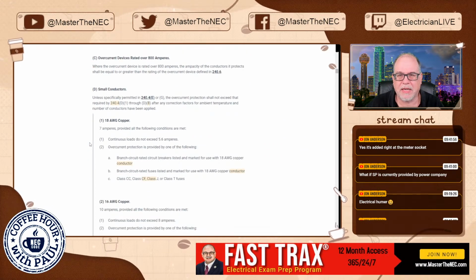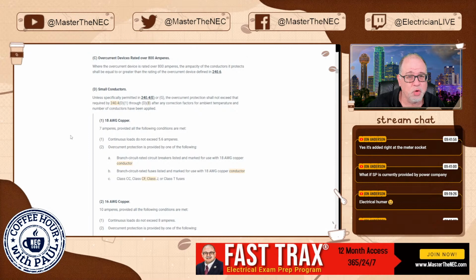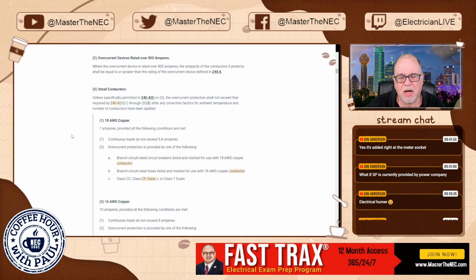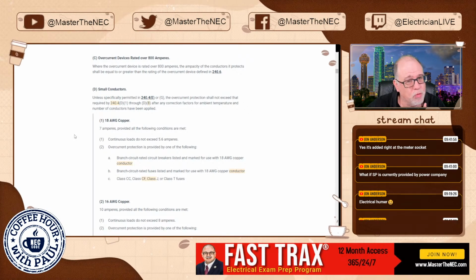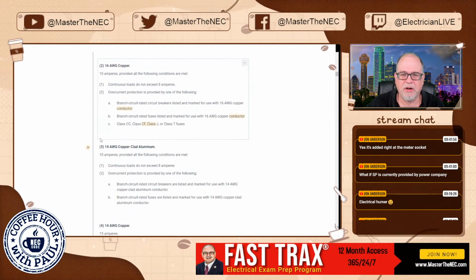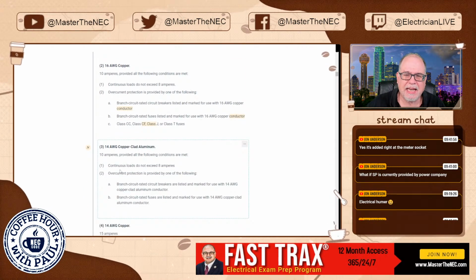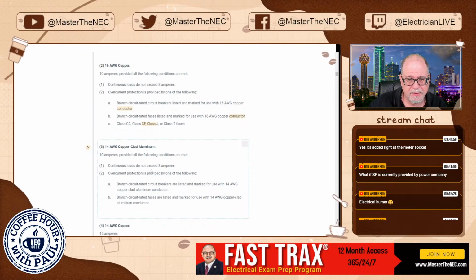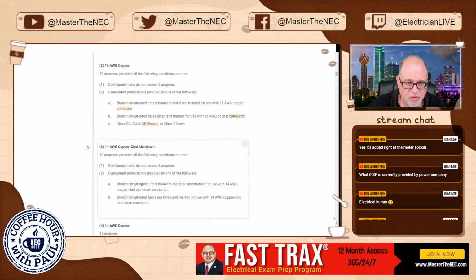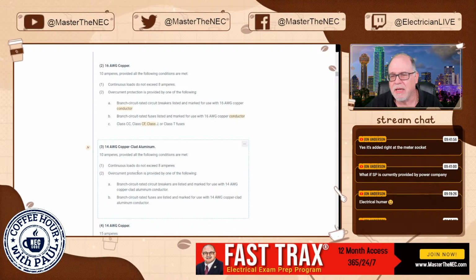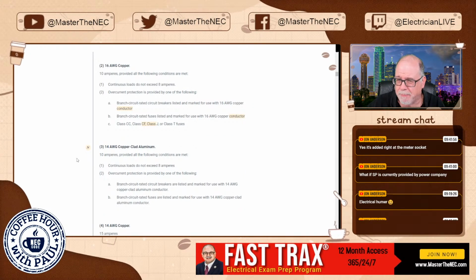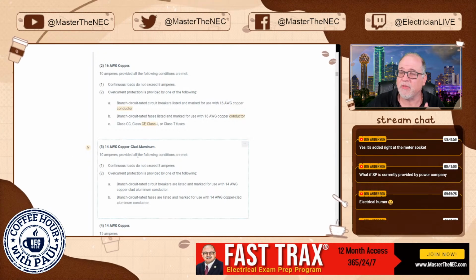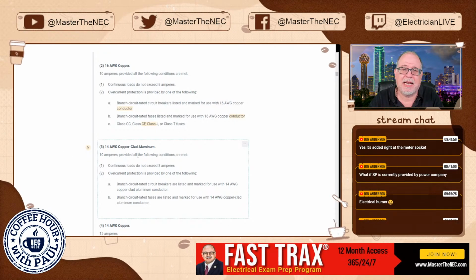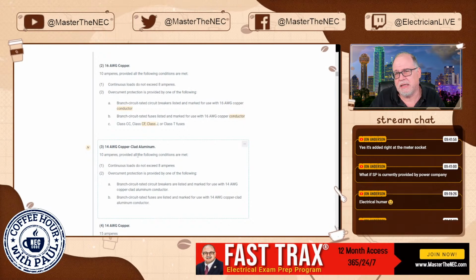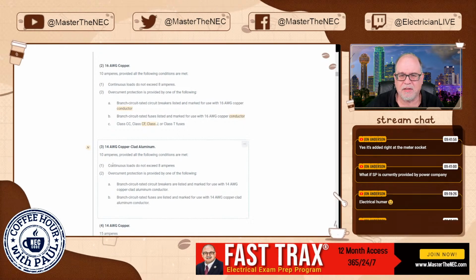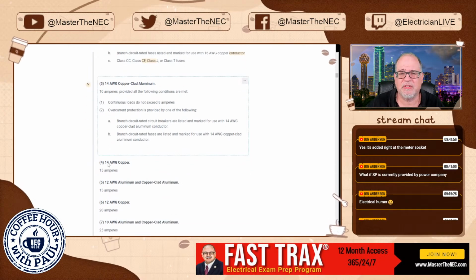The next thing that we want to look at is the inclusion of some new small conductor ampacity, overcurrent protection rules. I shouldn't say ampacity, overcurrent protection rules. So you'll see here that 14 gauge copper clad aluminum was added for 10 amps. Okay. And continuous loads, you can't exceed 8 amperes. And this is only really for lighting type of loads. But at least now we're giving you some ampacity ratings for these conductors. And it's very common to use 14 gauge copper clad aluminum for some control applications, right? So here you've got some ampacity. So that's now added into the National Electrical Code.